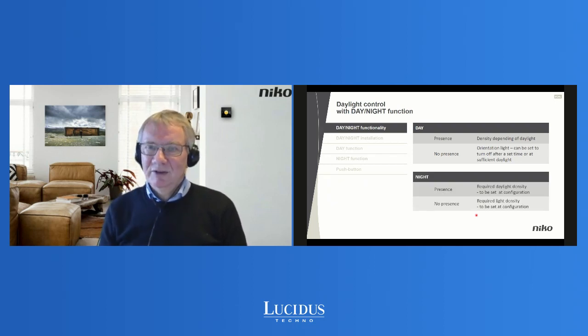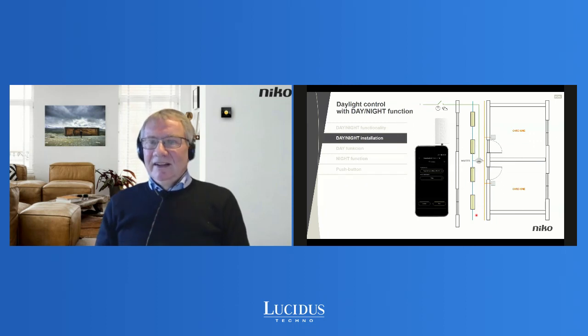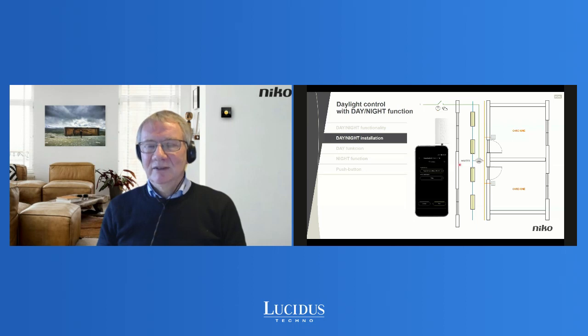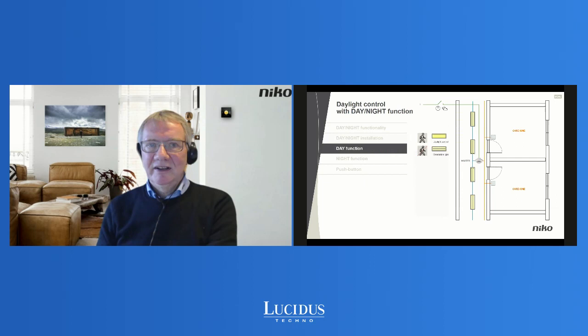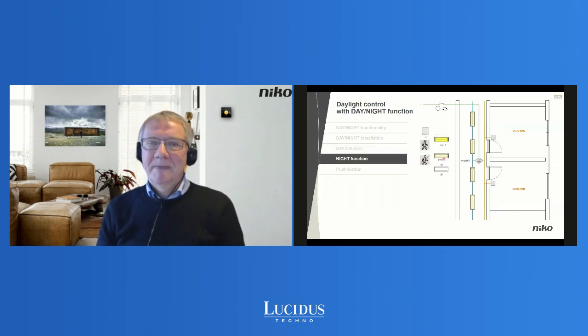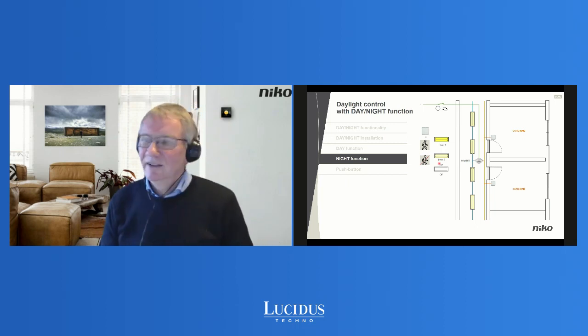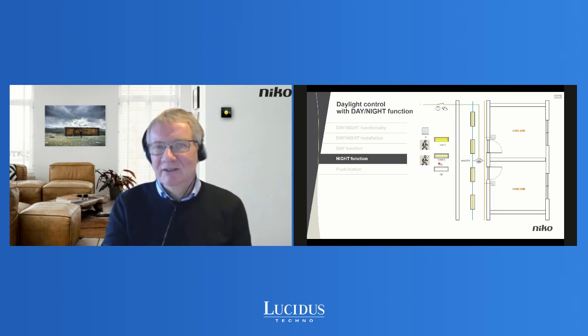In night mode, when somebody is present, you have a certain light level. It could be a higher level, and when nobody is present, a lower light level can be configured. Here it could be a hallway in a care home, and we have a day and night switch here to tell when it is day mode and when it is night mode. That is configured here by the app. In day mode, when somebody is present, there is daylight control, and when nobody is present, we have an orientation light level. In night mode, you can either activate the night mode by just detecting motion, or you can have a push button in order to activate light level 1. When nobody is present, you can go to a certain light level, or even switch it off if that is necessary or wanted.